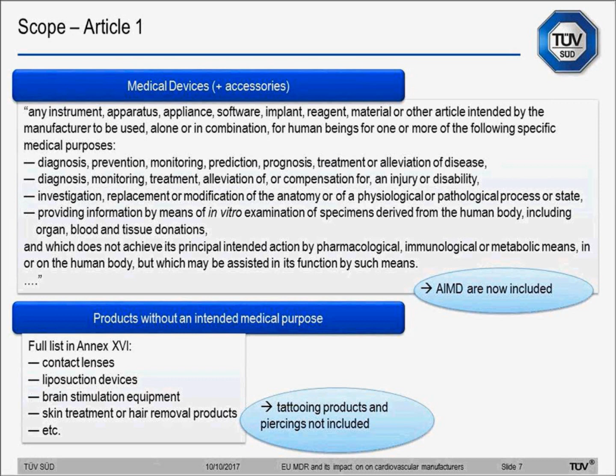The MDR covers medical devices and their accessories. The definition of medical device has been slightly changed, but I would not expect that to have an impact on the most traditional cardiovascular devices. If your device is particularly innovative or it's in some way special, you might want to have a better look at the definition and see if there is some impact, as the scope is not literally identical to the one of the Medical Device Directive. The main changes in the scope are that now active implantable devices are included and are not covered anymore by a separate piece of legislation, and that the MDR now also covers products without a specific medical purpose.